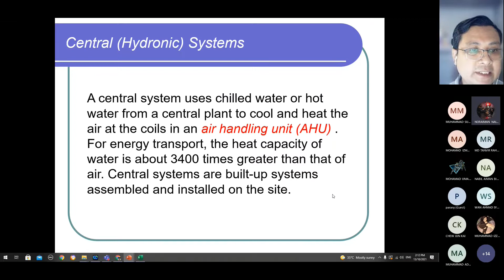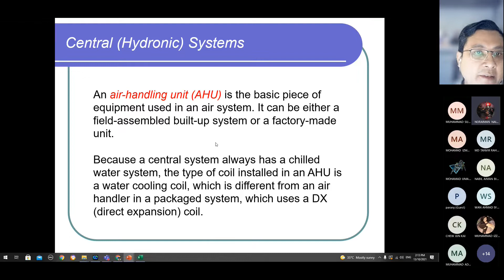So the air handling unit, AHU, is the basic piece of equipment used in the system. It can be either a field-assembled built-up system or a factory-made unit. Because the central system always has a chill water system, the type of coil installed in the AHU system is a water cooling coil, which is different from an air handler in a package system, which uses a DX direct expansion coil. So in the AHU system, we will develop many devices inside, so we can control anything, like the given temperature, the humidity, and also the amount of air supplying. So this one is already one package given in the AHU system.